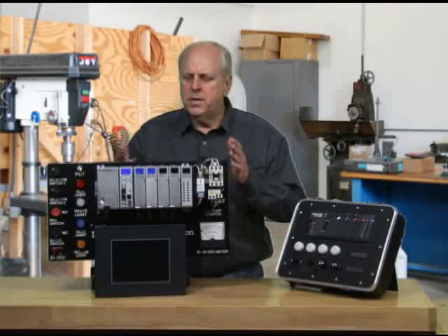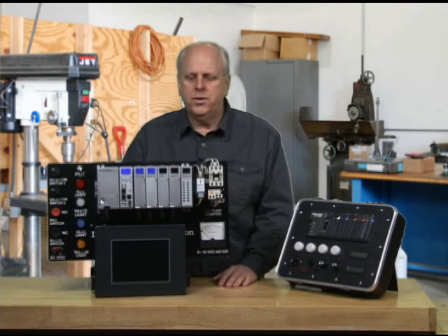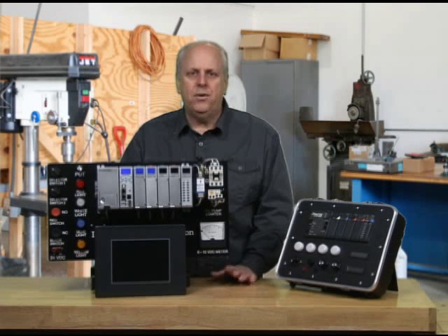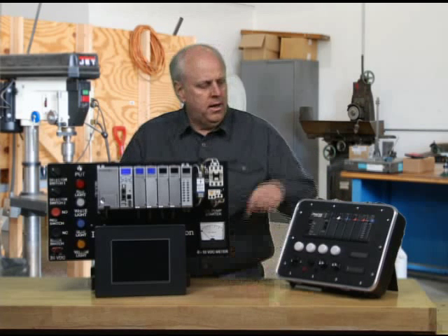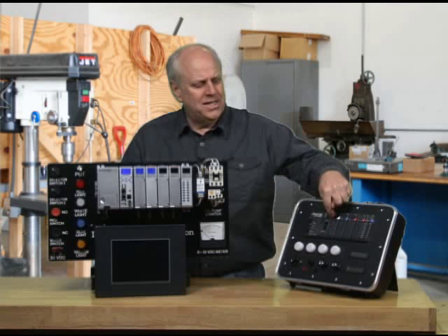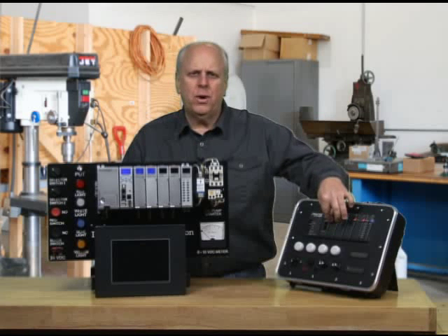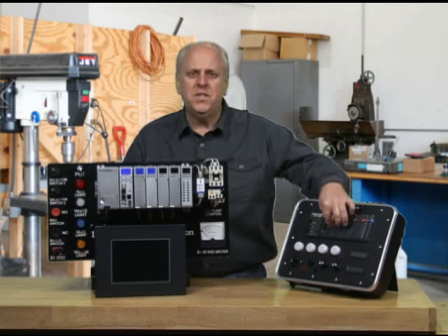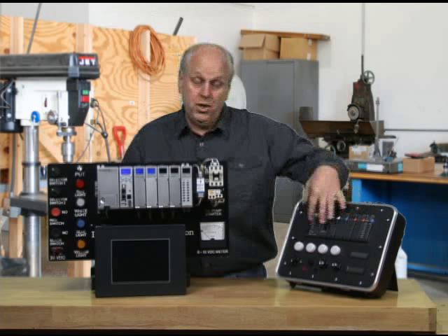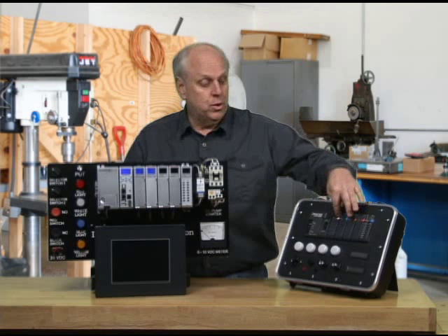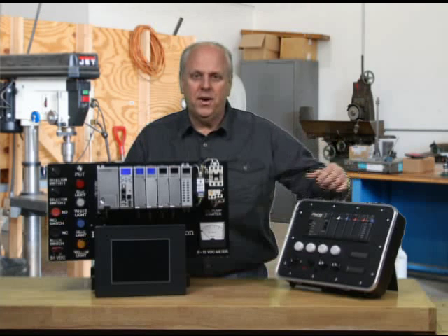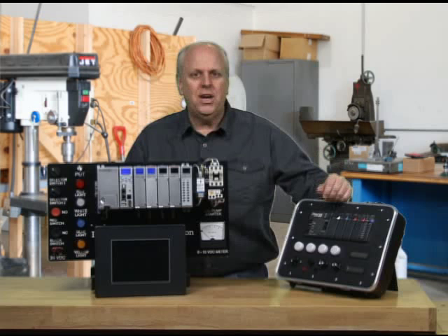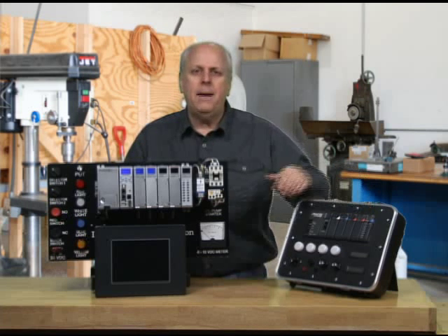Let's take a moment and go over some of the features of the Productivity 3000. One of the big ones is what's called tag name based addressing. On the older systems like this, when you went to program it, each input card would assign X's and Y's. Inputs were X's, outputs were Y's. It would assign physical addresses. And in this unit, it was octal based, so you would go 0 through 7, skip 8, 9. It was very, very archaic and very difficult to learn. Once you learned it, you had it down pretty well, but it took some time to learn it.